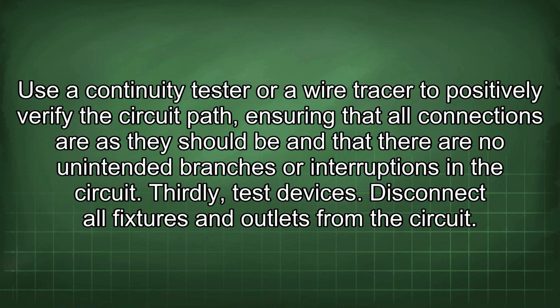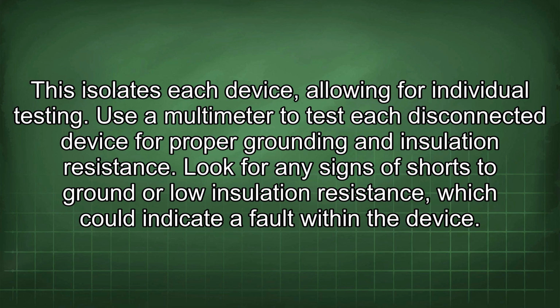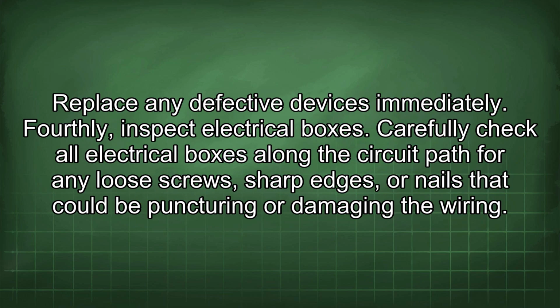Thirdly, test devices. Disconnect all fixtures and outlets from the circuit. This isolates each device, allowing for individual testing. Use a multimeter to test each disconnected device for proper grounding and insulation resistance. Look for any signs of shorts to ground or low insulation resistance which could indicate a fault within the device. Replace any defective devices immediately.